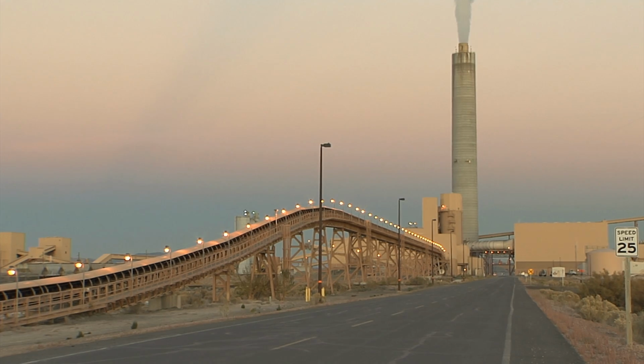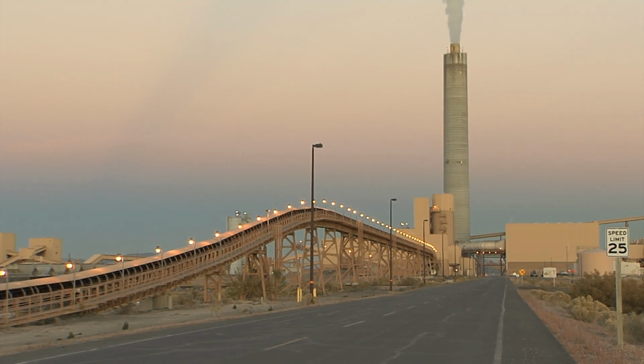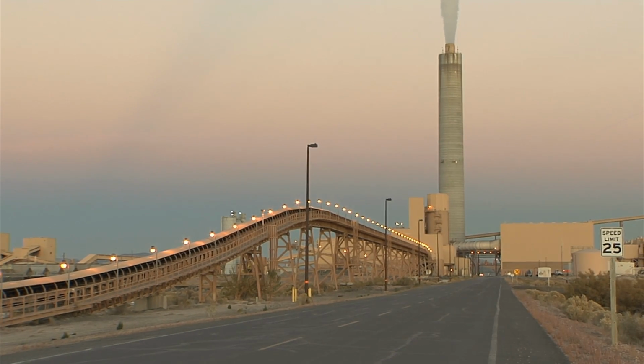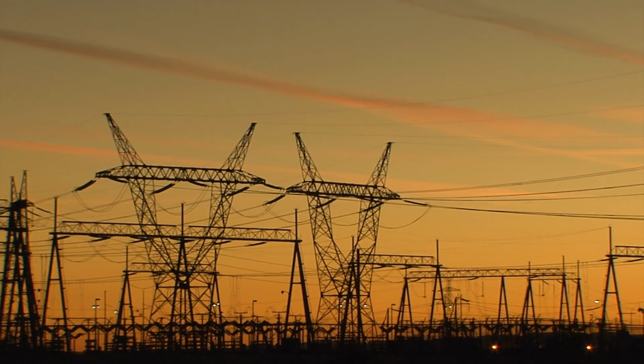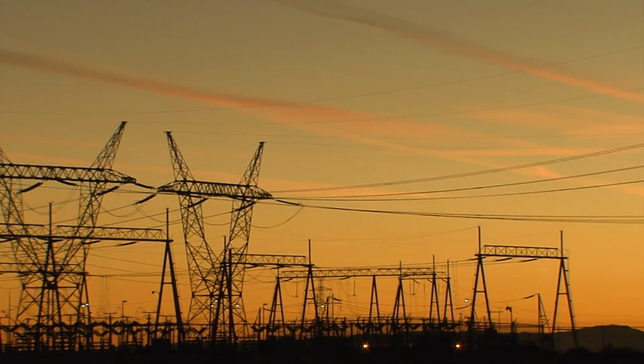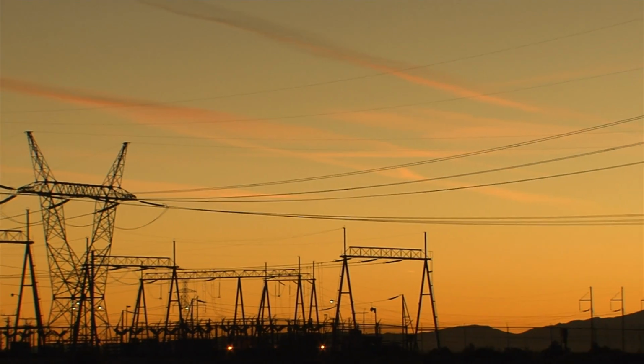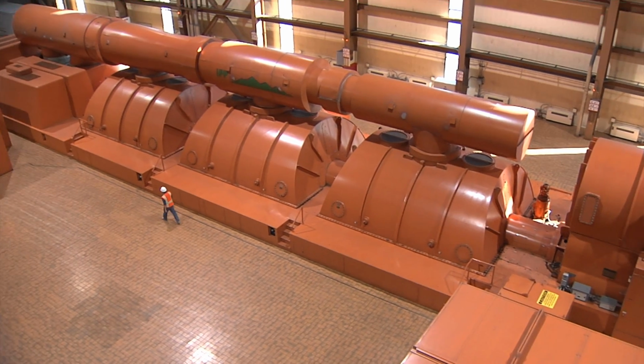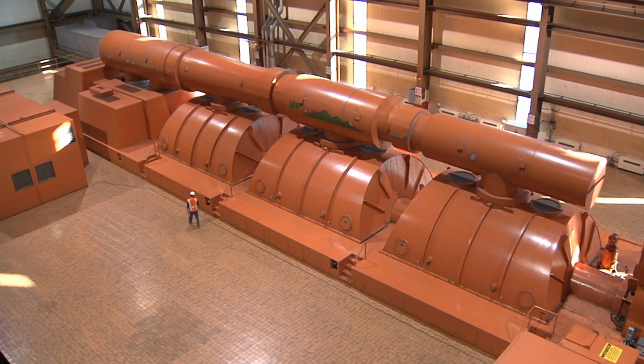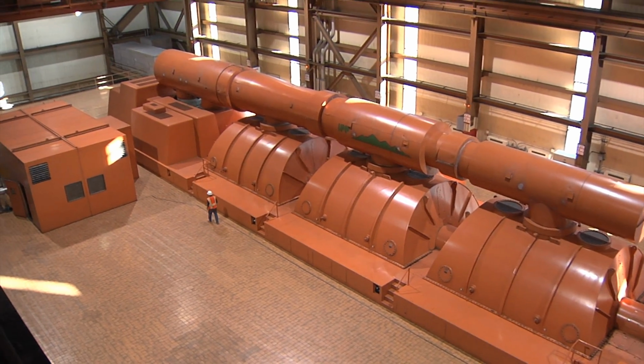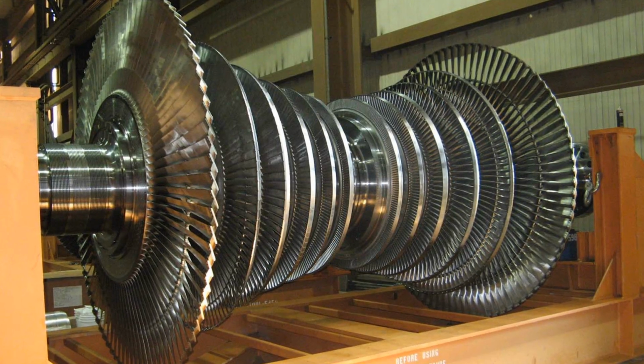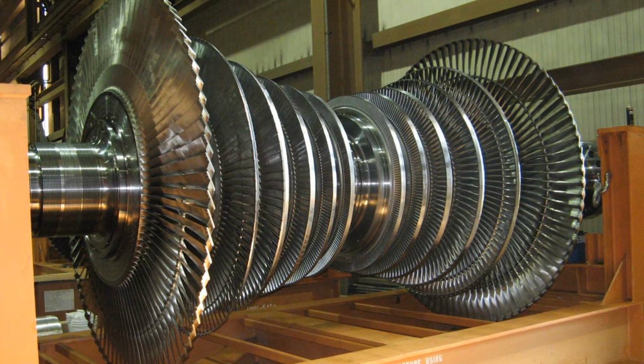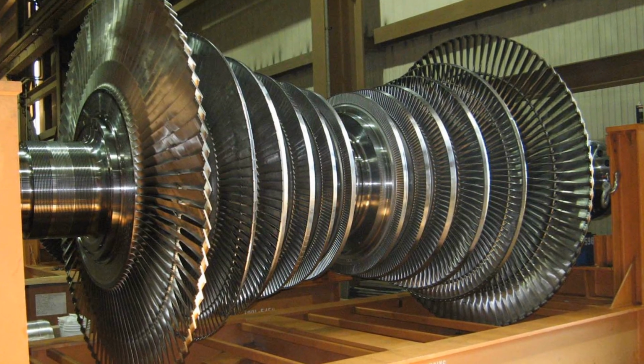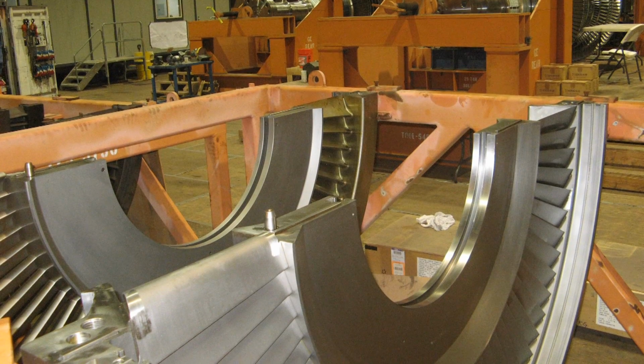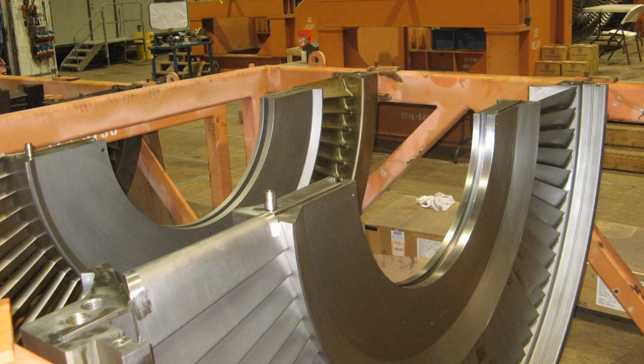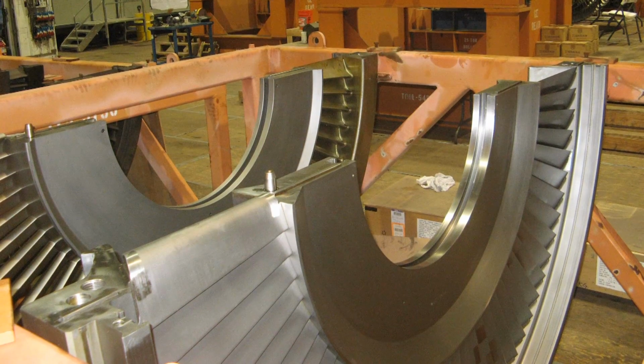Net unit heat rate for the generating station is at 9,775 BTU per kilowatt hour, a noticeable improvement from the last 2 years. Several factors contributed to this improvement, including the installation of the 3 replacement Toshiba LP rotors during the Unit 2 6-week major outage. The last stage buckets, which were originally installed in November of 2010, were transferred to the new rotors. The L1 pressure plates in LP turbine C were also replaced with new diaphragms.